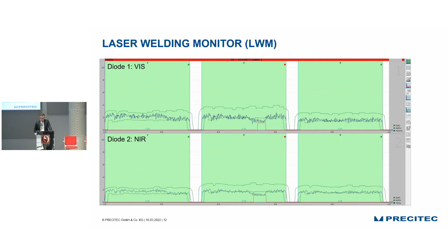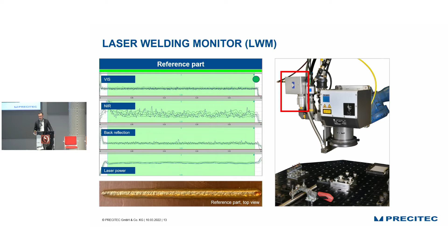Now, how does this sensor work, what can it detect and what can it not detect? So what are the limits? Here we perform the weld with infrared in copper, and you can see the three sensor signals: diode 1 visible, diode 2 near infrared, diode 3 which is sensitive to the wavelength of your laser source, and finally we can also track the laser power. This was a good weld, everything is in between the green envelopes.